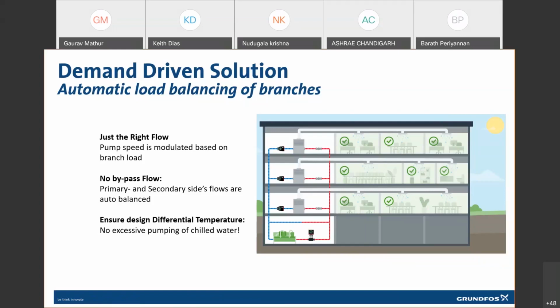But for the purpose of this time in the presentation, these pumps are controlled by the localized temperature sensor across the decoupler. So what you see essentially here is that all the pumps are distributed in the circuit and they all have a localized control. So you do not have a remote sensor which is controlling a pump at a distance, and all the pumps are controlled by temperature. And that is exactly the most important thing when we do a demand-driven solution. You do not have an indirect way of controlling the pump.